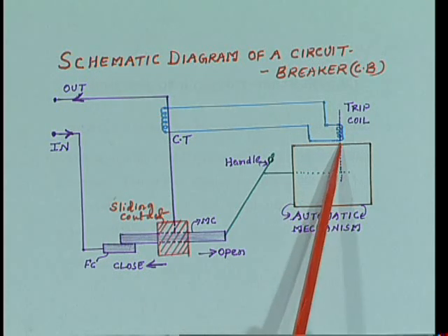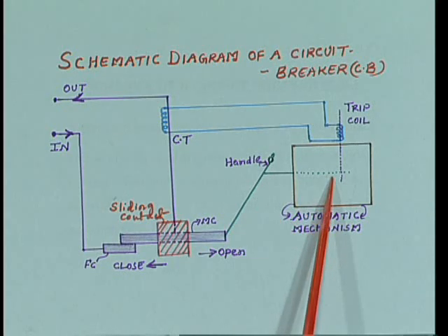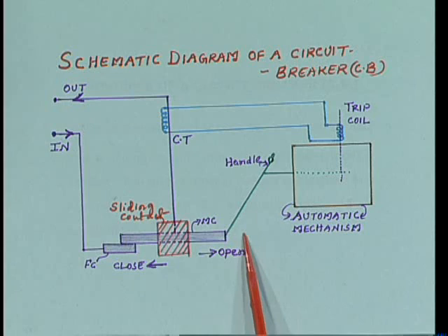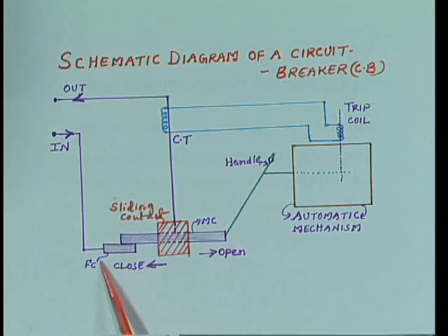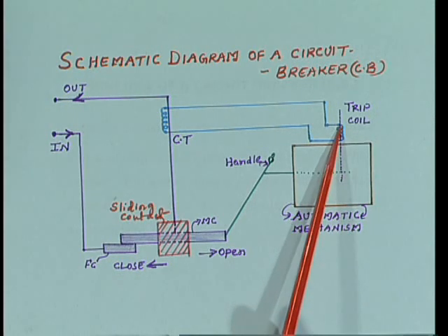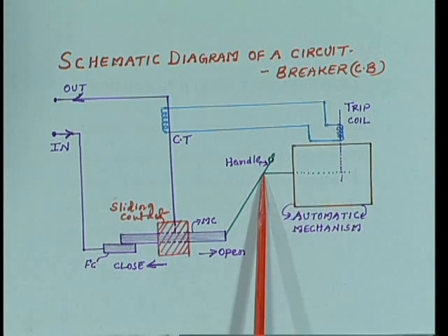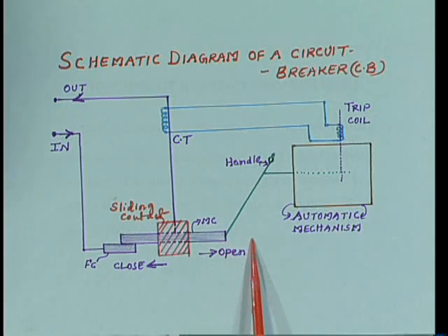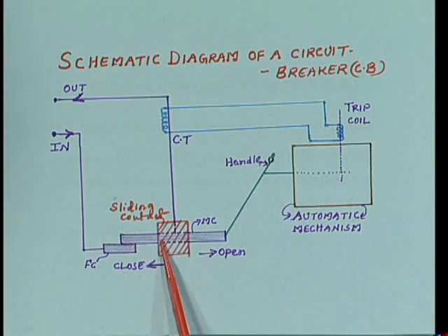Once it energizes, it pulls the handle. Once it pulls the handle, automatically the handle will be moved. Once the handle is moved, the moving contact is separated from the fixed contact. Now these two are no longer in contact with each other.